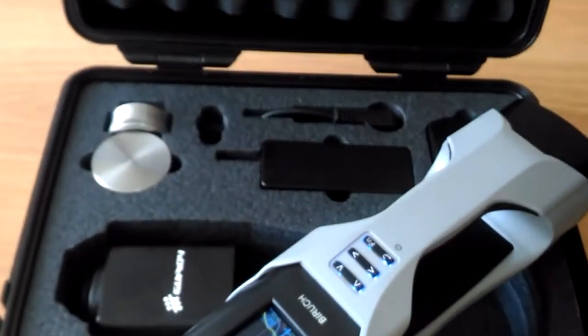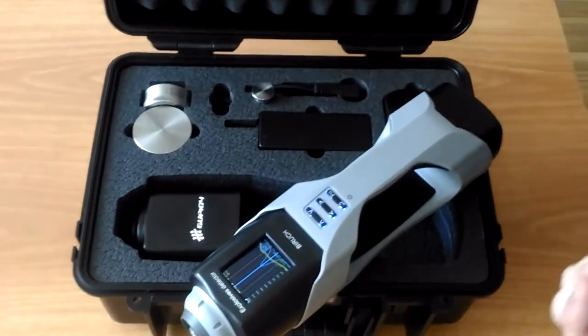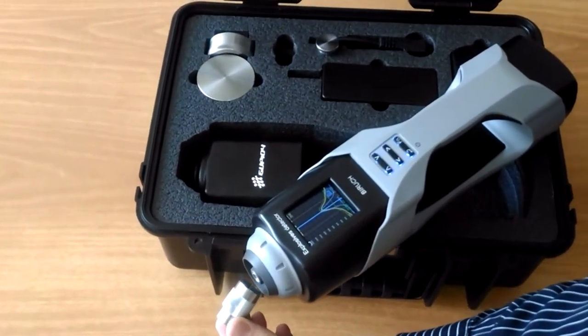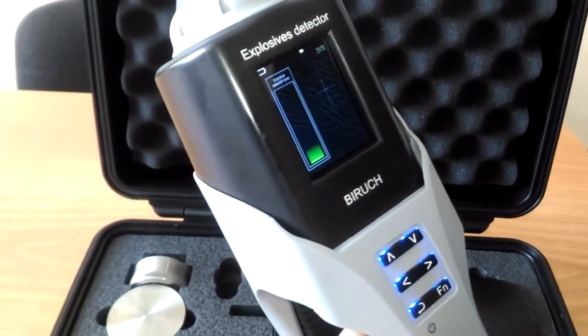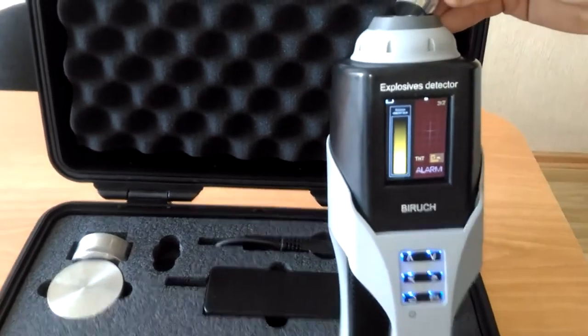To test the detector's operation, we use a TNT Trotyl Vapor Imitator. We bring the imitator to the input of the analysis chamber. The light and sound alarm indicates the presence of explosive content. We can change the display mode to the level scale — it shows the signal level and, when the substance is detected, it shows the recognized explosive and the signal strength.